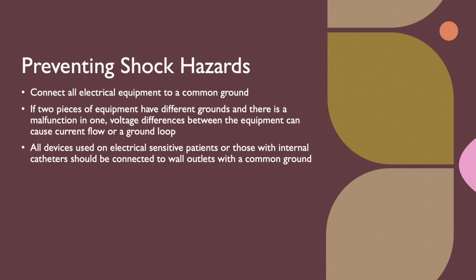Like I said, you're probably not going to be responsible for making sure all the equipment is connected to a common ground. That's usually handled before the lab opens during construction. But all electrical equipment is connected to a common ground, usually the lab's main power panel. The reason why having one ground is important is that different power sources may have different voltages that can cause a power disparity and an overflow to the equipment or patient.